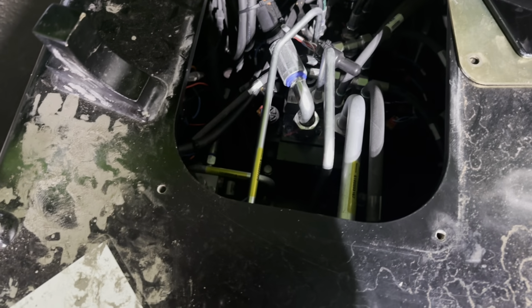The only thing I'm not getting enough power to, and what I'm checking here is inside the chassis. I will show you just a sec. So I'm checking the wiring here now, and what I found is, look, if I move the wires here, this one here... did you see that? It's something not right in that fuse holder, but it looks quite nice actually, like lightning. Alright, so I will check on that one just to see what's going on there. We're gonna get that fixed, and maybe that's gonna be it then.